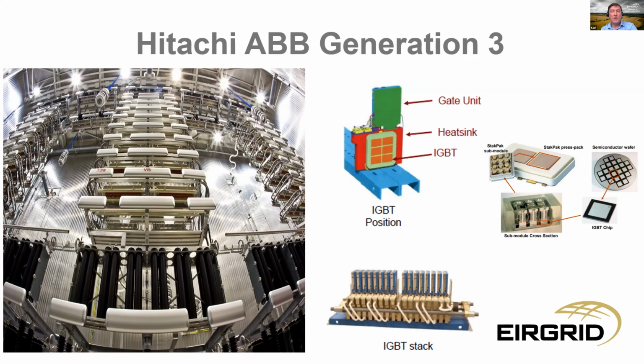Each stack has around 25 IGBT modules, and in total there are about 2,500 IGBTs in a converter station. Each IGBT has in excess of about 100 components made from transistor and diode semiconductors and mechanical components within the StakPak. During switching operations, temperatures within the valve hall can reach about 70 degrees Celsius, and the valve systems are being force cooled by 2,000 liters of high pressure glycol.